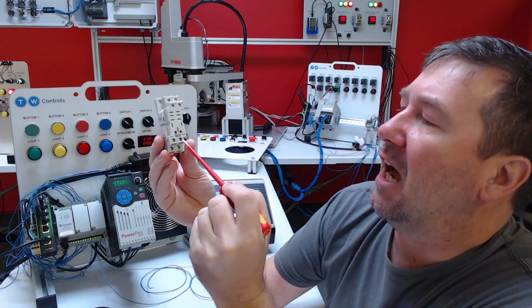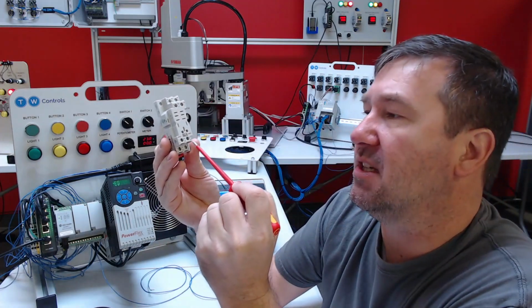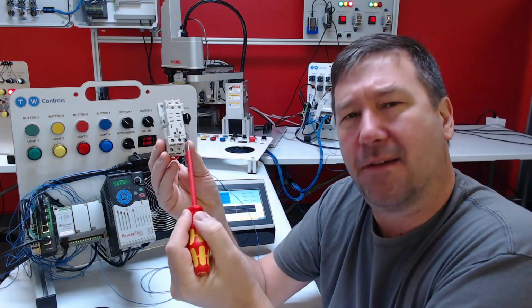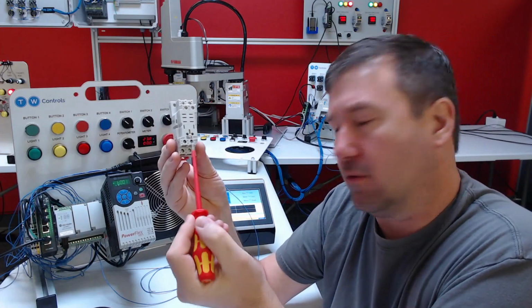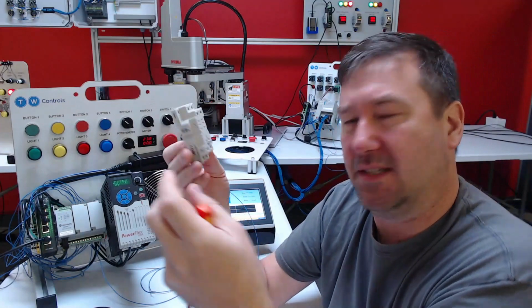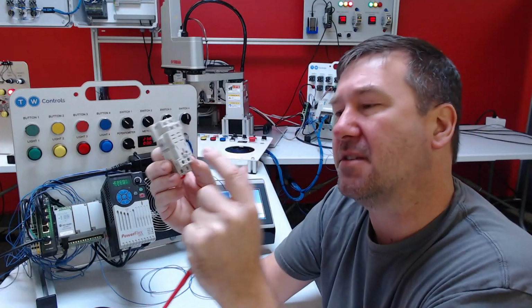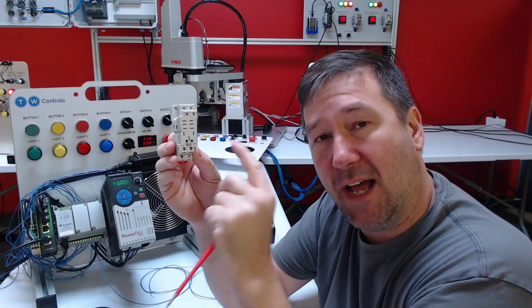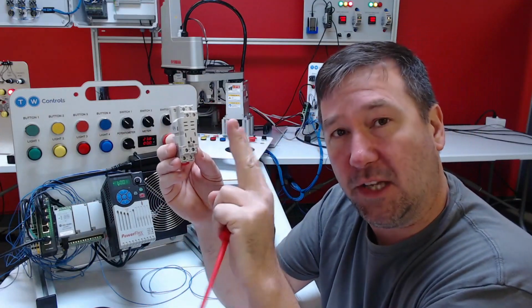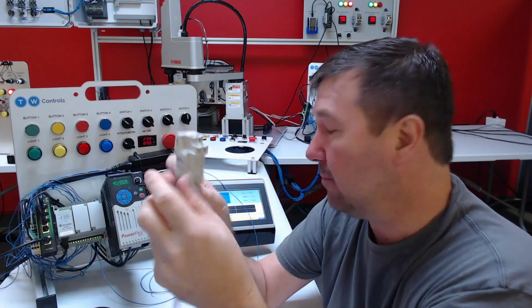So I'm going to connect output 4 to terminal number 13 or A1. Now notice that is the right terminal on this particular relay. Some of them are opposite, and it can matter, especially on DC, because sometimes you'll have a diode and the polarity will matter. On this particular setup, it does not matter.